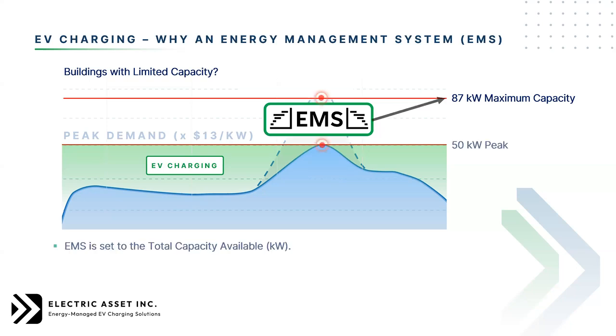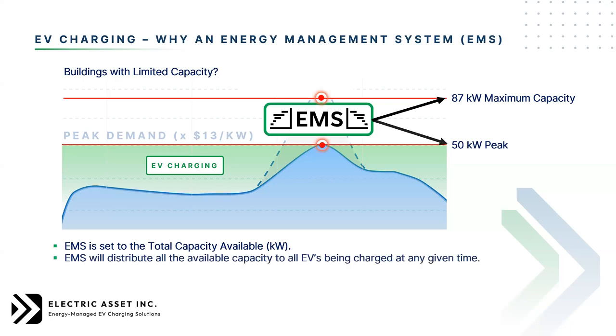So now the EMS knows the breaking point is a maximum of 87 kilowatts, but the ideal position is 50 kilowatts. But the 50 kilowatts is a variable based on dollars. So if you want to save money, you keep the peak demand as low as possible. The 87 kilowatts is a fixed amount because that's your capacity. So it's a safety feature so that you won't exceed your capacity in the building.